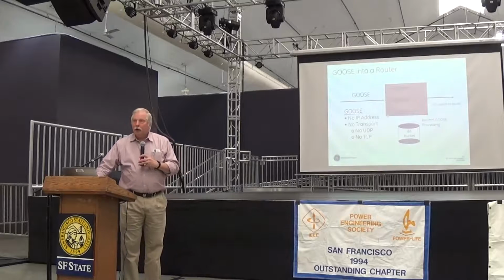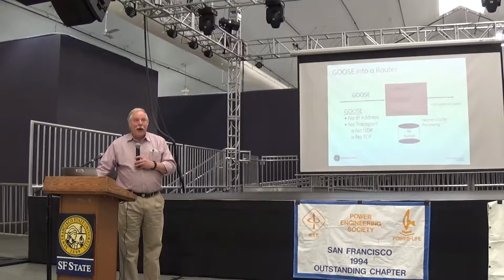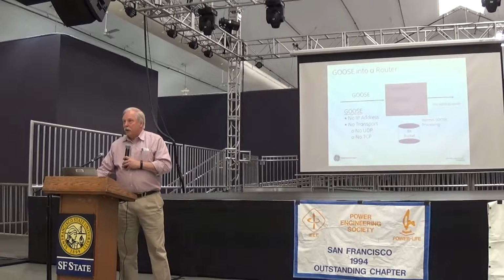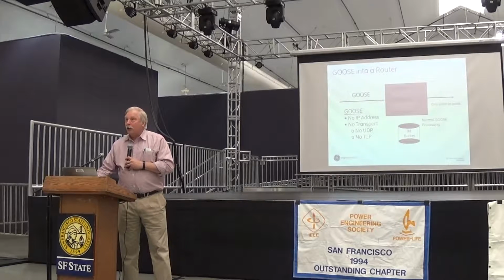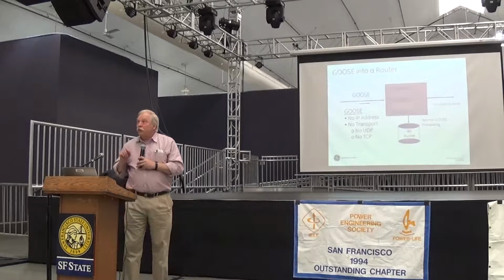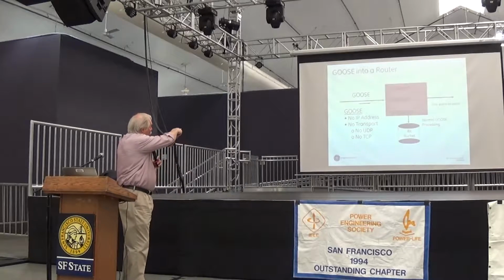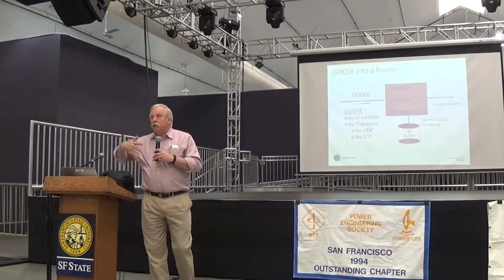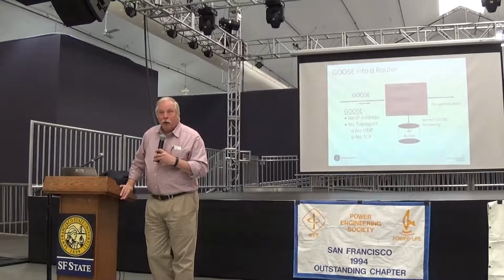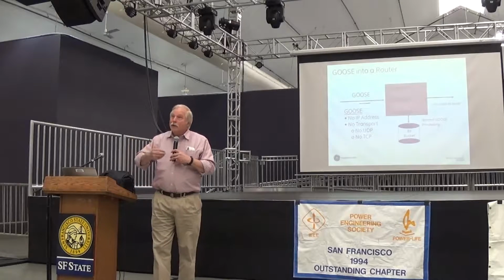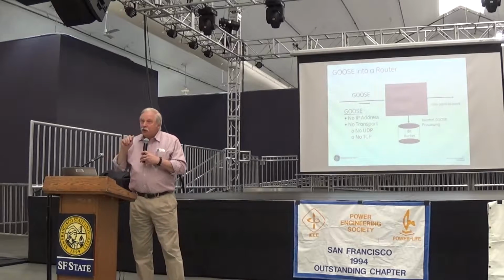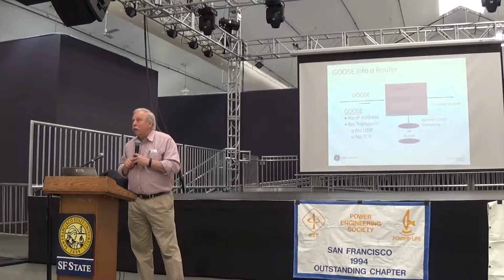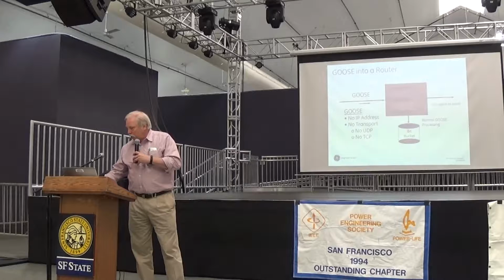Today, as I'm sure Alex mentioned, when you have GOOSE in a substation, it operates only on a local area network. When you send a GOOSE message into a router, it has no idea what to do with that GOOSE message. As a result, that message winds up in the bit bucket, literally gets thrown away by the router. What needed to be done was to change the messaging format of the GOOSE to allow it to go through the router.